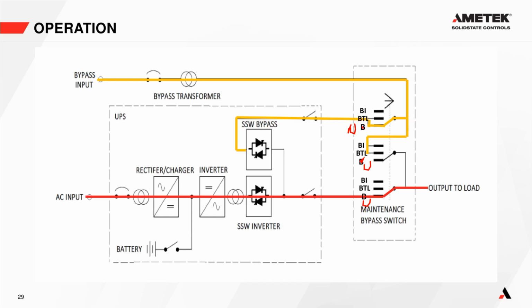Okay, so we have normal, then we have BTL, which is bypass to load, and then we have BI, which is bypass isolate. Okay, so in the normal position, normal, normal, and normal, power will flow out from the inverter through the static switch, out through this bottom normal contact here, which is closed, out to the load circuits. Okay, that is the main power flow.